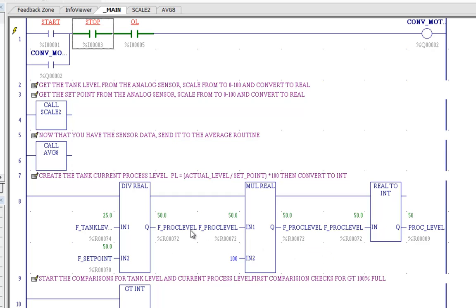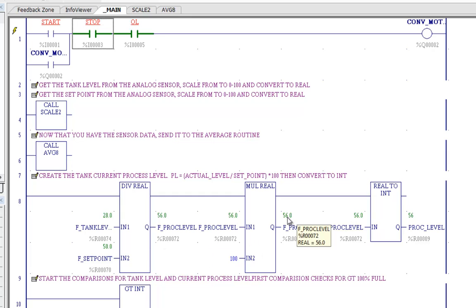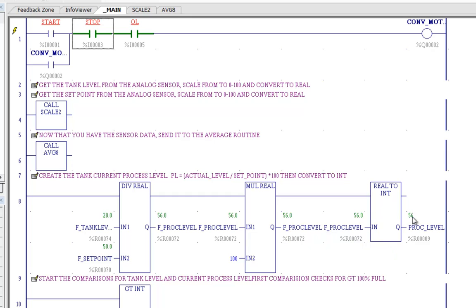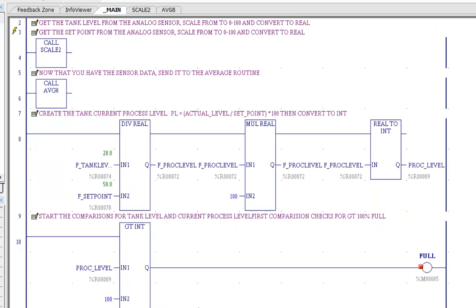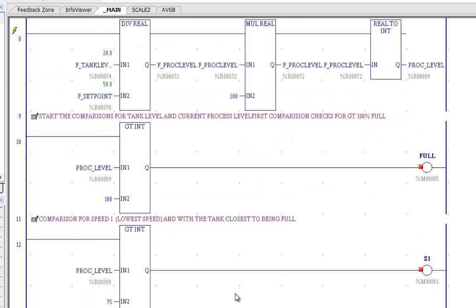And what we're now seeing is the output of our divisor, of our division here. Output of our division is going to be a fractional number. The PLC then multiplies it by 100 so that we can use a value from 0 to 100. And then the last thing we do is we convert it to integer. The reason we convert it to integer is because our comparison, our relational comparisons are integer comparisons. So we take our integer process level and now we're going to use that for our comparisons.